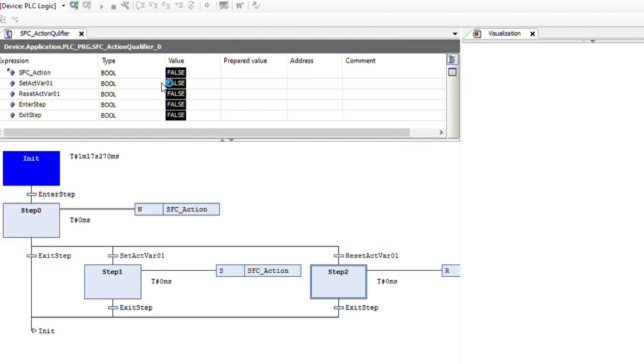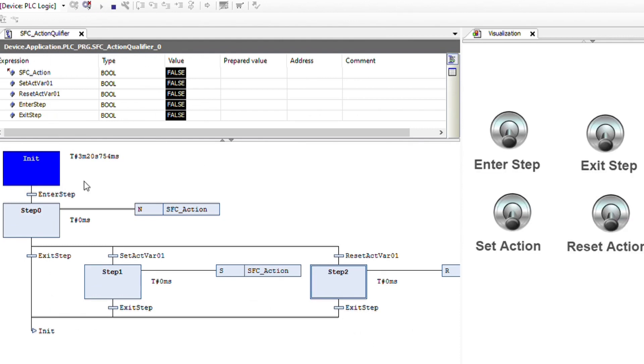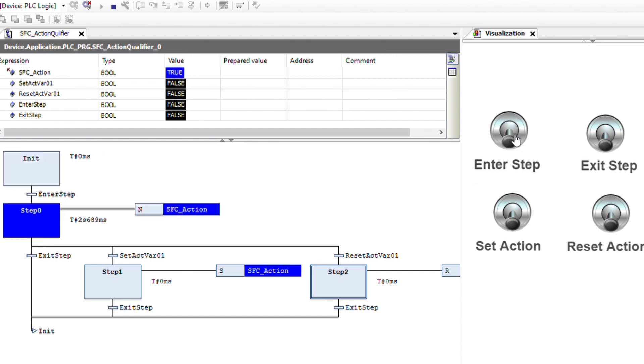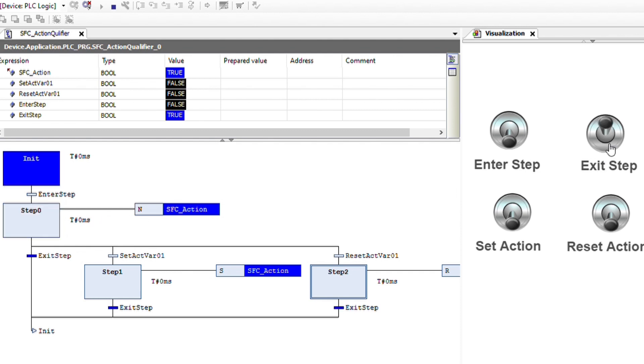Now let me log into the project and run it. Initially we are here. If I provide enter step, we will enter into the step, and you will see that during the time in which step 0 is active, SFC action will be true. And as soon as we go out of step 0, it will become false. Each time you see that while the step is active the action is true, and while it is deactivated the action is false. That's basically how the N qualifier works.